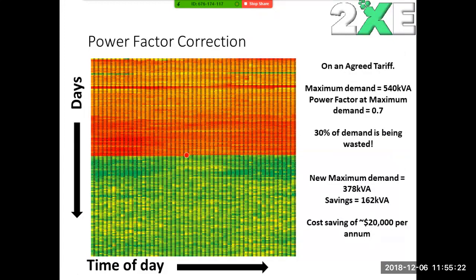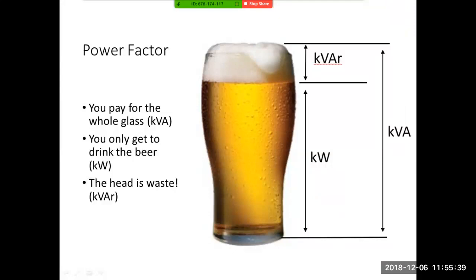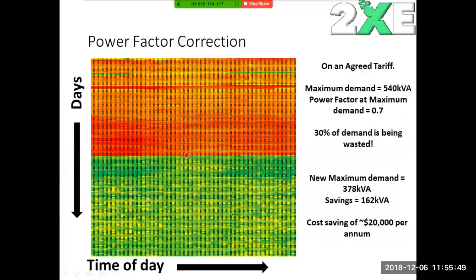At the start of vintage, this winery had a poor power factor. They had an average power factor of about 0.7, which is really quite poor. And this meant that they had a maximum demand of 540. So if we go back to this graph, that means that 0.7 of their kVA was being used in kilowatts, while 30% was being wasted on the kVAR, or the head of the beer, basically. And so what you can do in that instance is install power factor correction. That reduces the head of the beer and basically brings the power factor up to about 0.98.